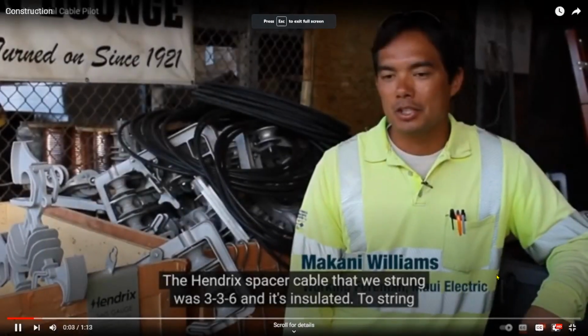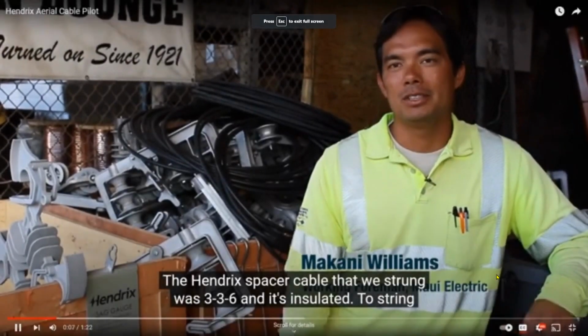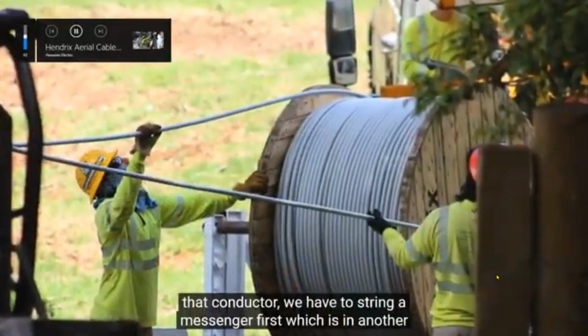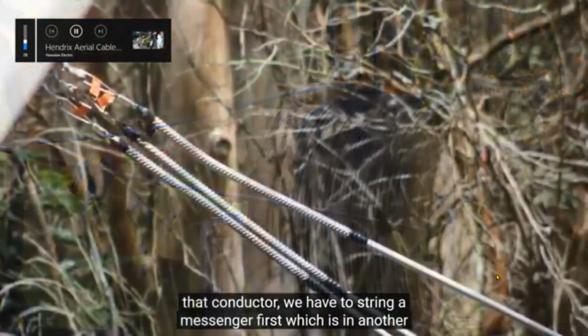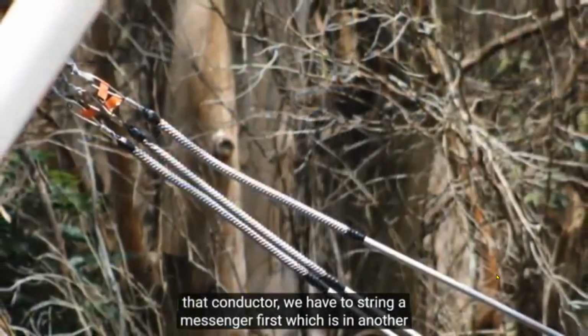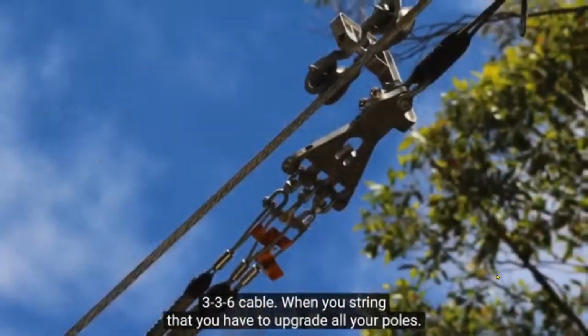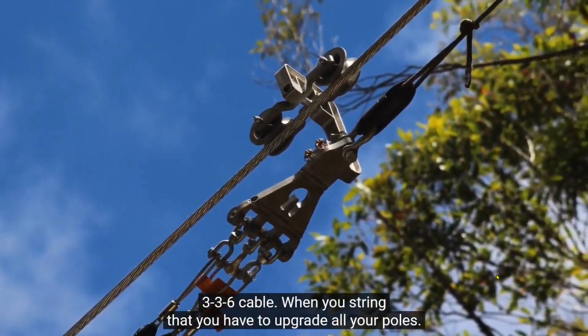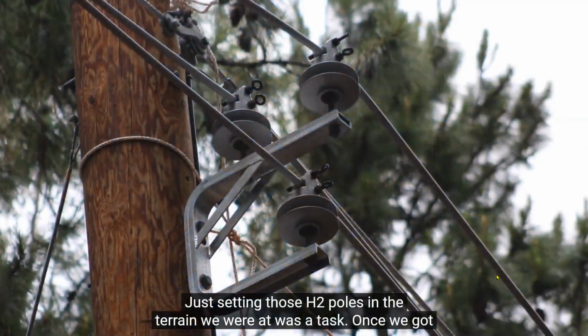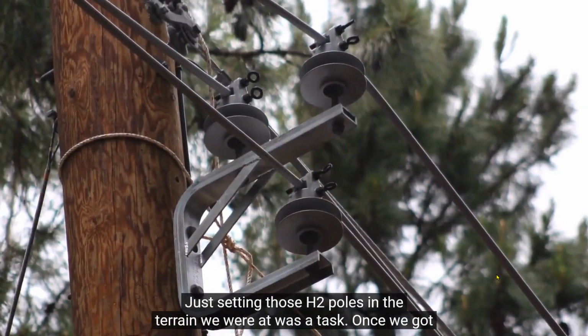The Hendrix spacer cable that we strung was 336 and it's insulated. To string that conductor, we have to string a messenger first, which is another 336 cable. When you string that, you have to upgrade all your poles. Just setting those H2 poles in the terrain we're at was a task.